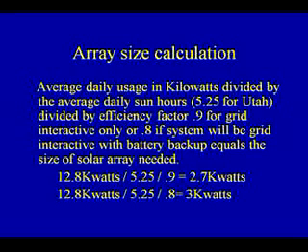For grid interactive systems, those which sell to the grid during the day and buy from the grid at night, we use an efficiency factor of 0.9. If the system will be grid interactive and will have battery backup for emergencies, the efficiency factor will be 0.8.